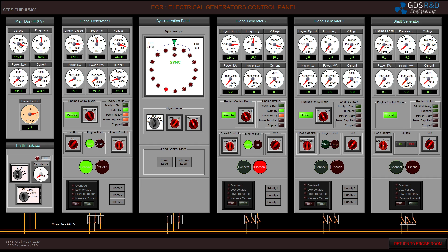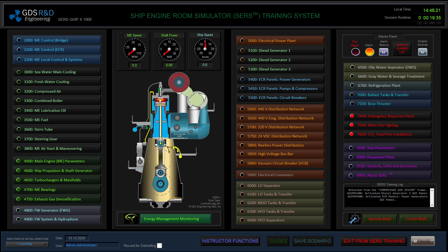It is at 60.4 Hz — very close. A couple more adjustments: 60.2 Hz. It is now synced. I am ready to connect diesel generator number two. I want the two generators to share the load, so I will select the equal load program and wait for the two generators to share the total load on the main bus bar. Everything looks stable so I can continue operations.